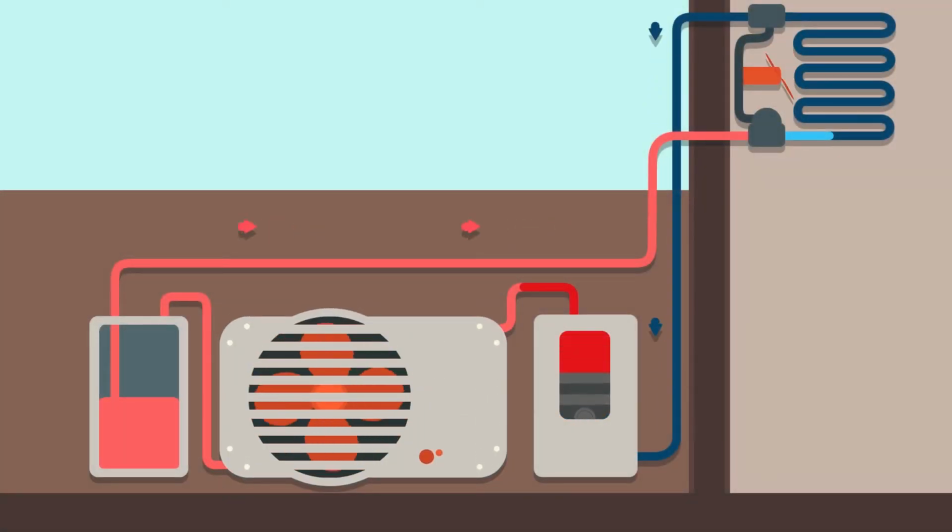Afterwards, the warm, high-pressure liquid passes through the pipe to an expansion valve, which is also called a metering device, that allows the refrigerant to enter the evaporator at a controlled rate. The pressure is much lower than in the condenser. The refrigerant expands in volume as it passes through the expansion valve.